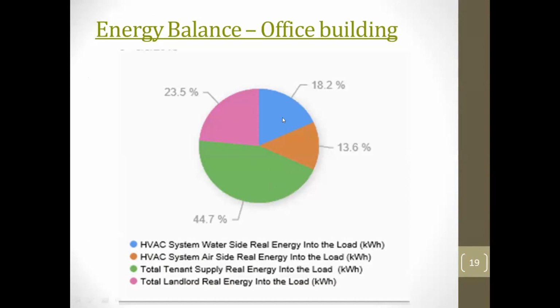In this particular building, you can see the HVAC side, air conditioning. This is the water side, this is the air side. Total comes to about, I think, 33%. Very much lower compared to the tenant and the common area consumption. But the same building about 15 years back had this somewhere around 55%. Right? Because the AC system was not so efficient.